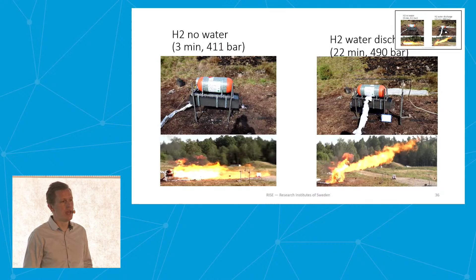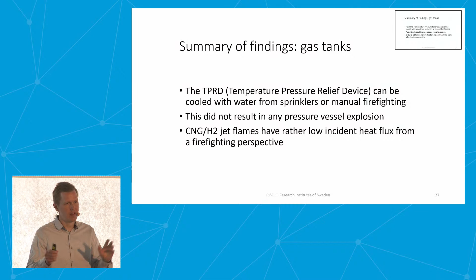So it was really worst-case conditions. The conclusion was that we didn't have any explosion, and this TPRD, temperature pressure relief device, can be cooled based on these tests during firefighting without risk of explosion. We could also conclude that these jet flames have quite low incident heat flux, so compared to a diesel fire, for example, you can be quite close to the fire, but you should stay away from the jet fire flames, of course.